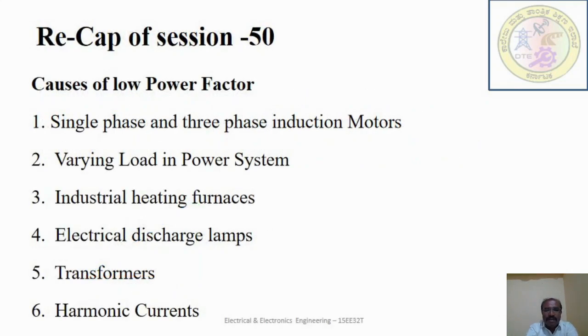Next, in the previous session, we discussed the causes of low power factor. There may be different causes: the use of single phase and three phase induction motors, and varying load in the power system is also one of the causes of low power factor. Industrial heating furnaces, electrical discharge lamps, transformers, and harmonic currents are the major causes of low power factor.